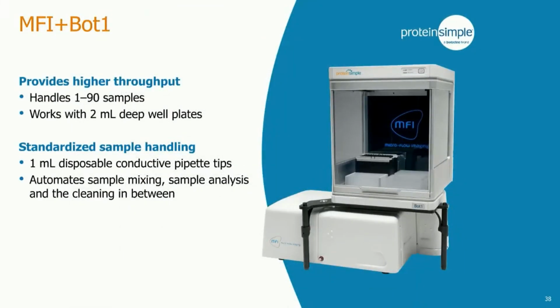For cases where higher throughput is needed, we offer the Bot1 autosampler, which bolts onto the MFI and can be easily removed when you need to run the MFI manually. The Bot1 uses a 96-well plate format and has an automated pipetter that handles sample mixing, cleaning, and introduction of the sample into the MFI. It allows you to automate up to 90 samples per run, and it works with 2 mL deep well plates. Automation provides the advantage of being hands-free as well as having consistency in sample handling.